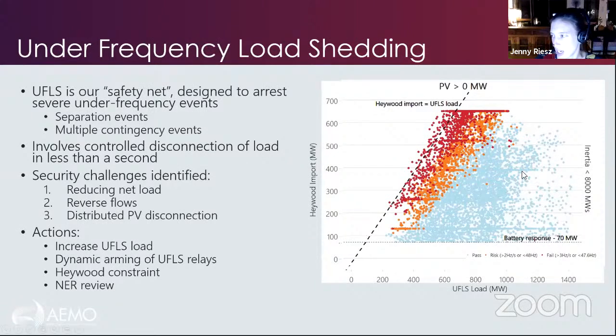This chart here is showing you studies that we've run looking at separation of the South Australian region if we lose the interconnector connecting to the rest of the grid, as a function of the flows on that interconnector, the Heywood interconnector, and the amount of load that's on our under-frequency load shedding scheme in South Australia. And you can see this line here is showing you where the imports are equal to the amount of load. And we would fully expect that any points above that line would fail, as represented by the red dots, and they do. But we also see a very large number of risky periods and fail periods that are on the other side of that line, where we do have enough load, but because of these other effects, those scenarios are not passing our acceptance criteria.